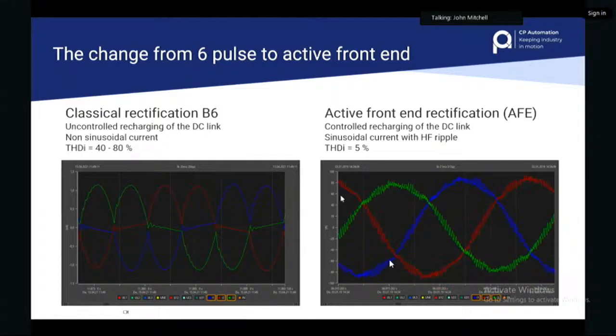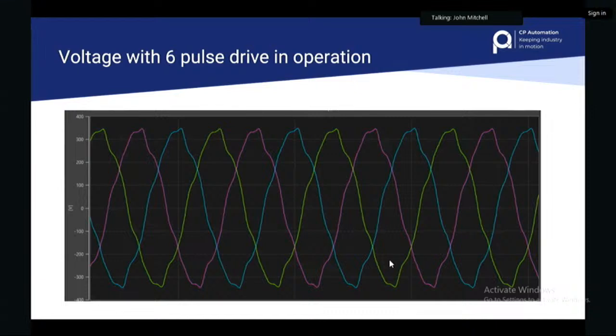On the right-hand side we have a different problem. The active front-end drive is giving a nice sine wave, but it has overlapping high-frequency switching of supraharmonics over the waveform, and that can be detrimental too to the transformers. It can cause gassing in the oil analysis, as an example. Not to mention many other disturbances because of the frequency that it's operating at.